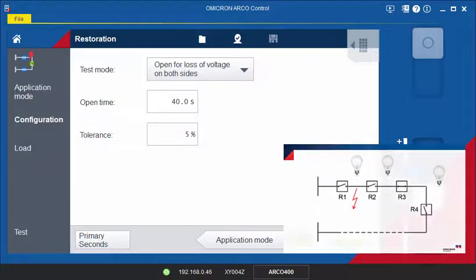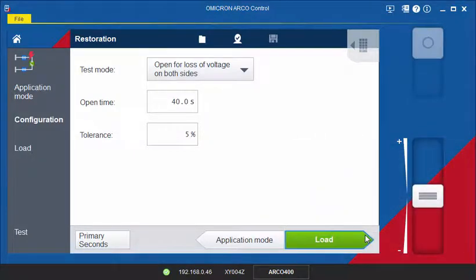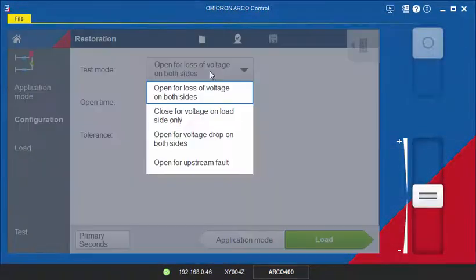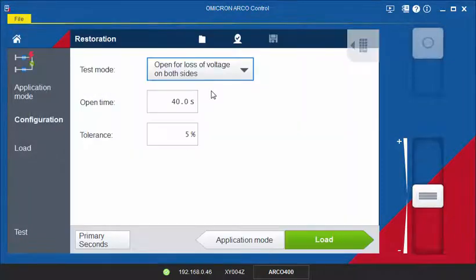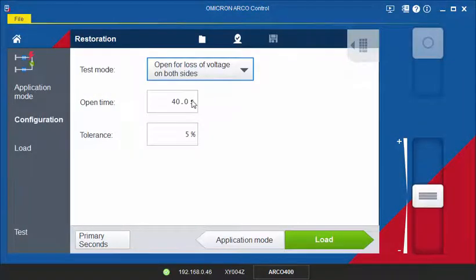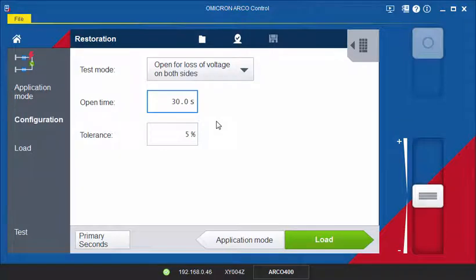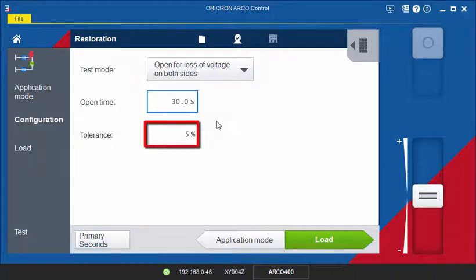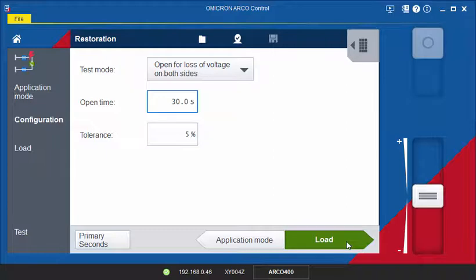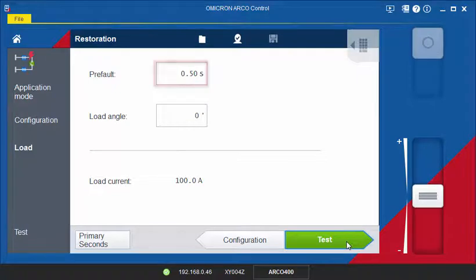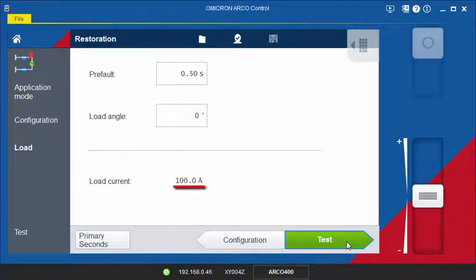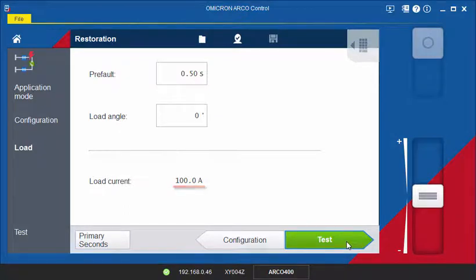On the Configuration page, select the test mode Open for loss of voltage on both sides. Enter the Open Time setting. This is the time which the control should open within according to the settings and the tolerance. Then, proceed to the Load page and specify the duration of the pre-fault state. Enter the Load angle. The Load current value is taken from the nominal values defined in the hardware configuration.